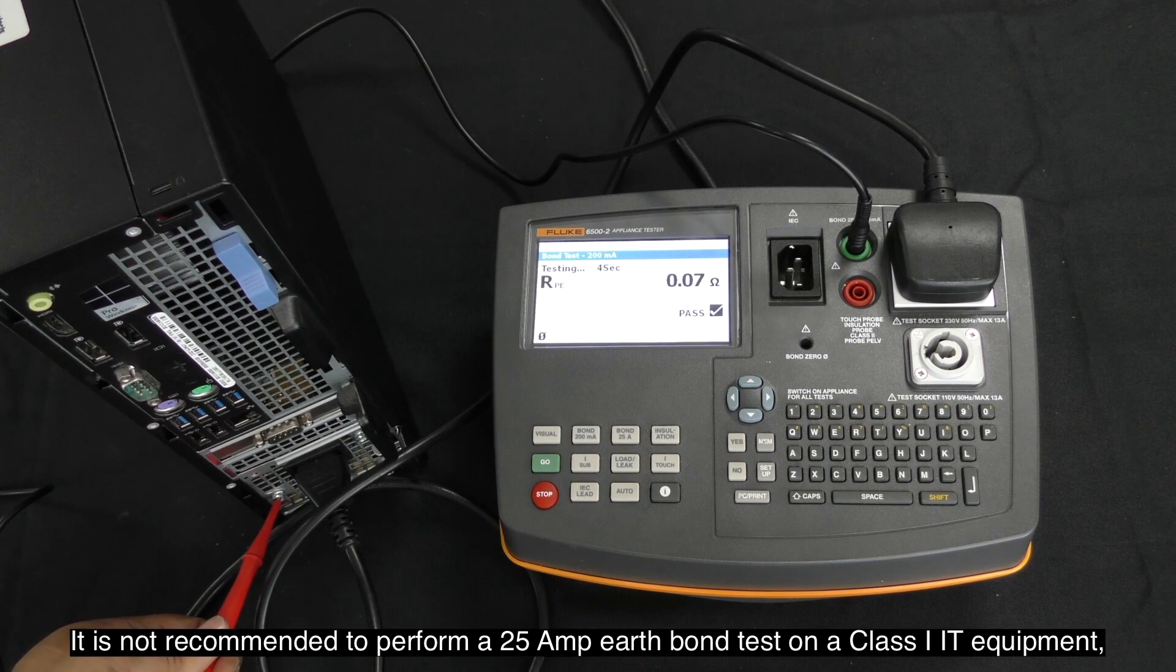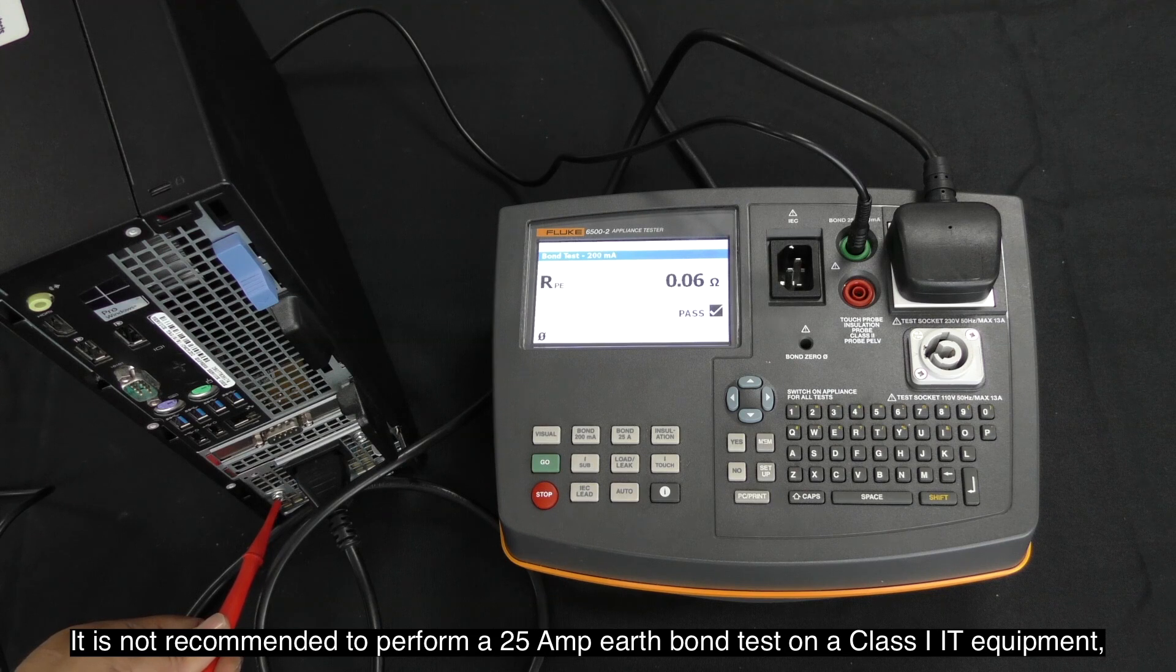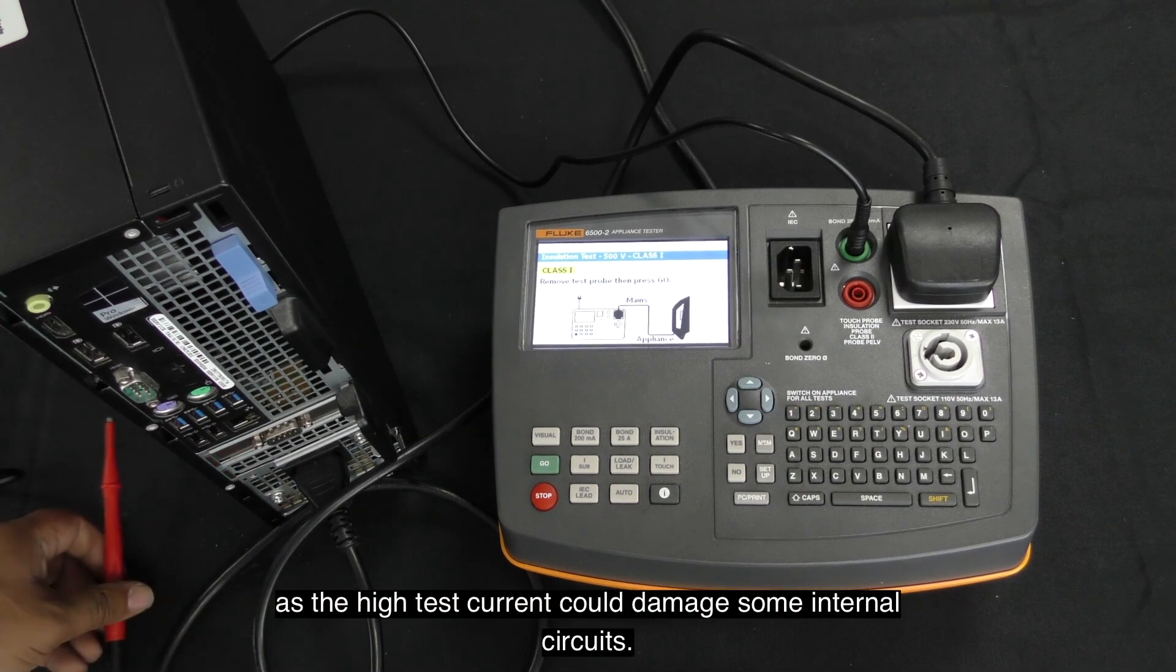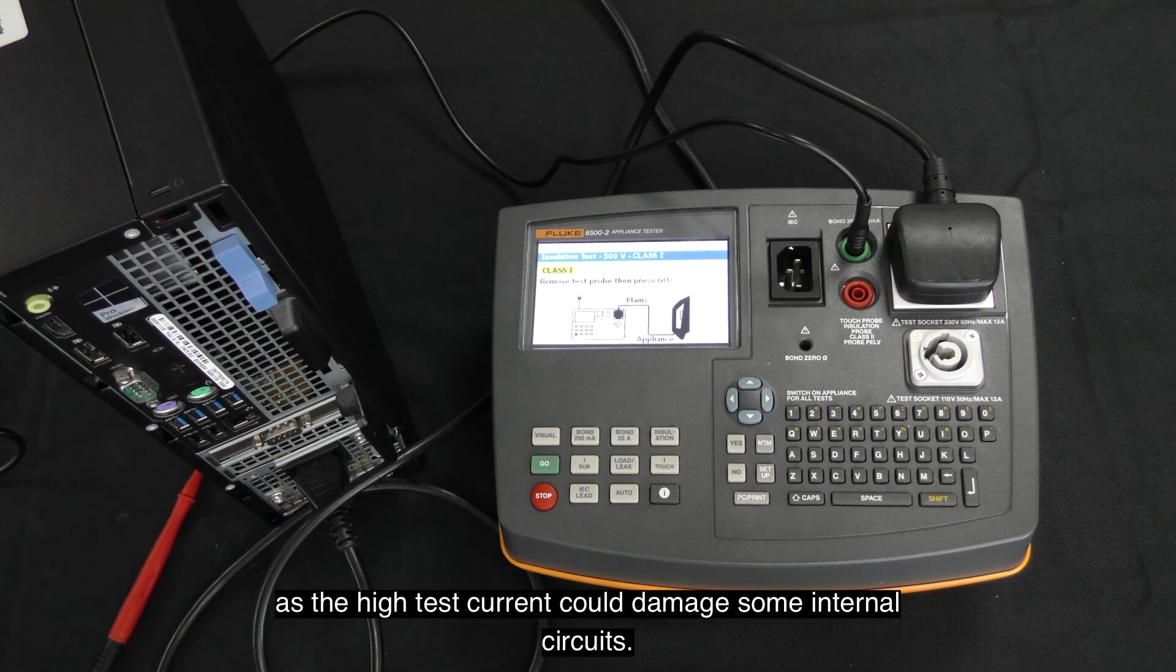It is not recommended to perform a 25A earth bond test on Class 1 IT equipment, as the high test current could damage some internal circuits. The Fluke 6500 Mark II goes on to the next test step, the insulation test.